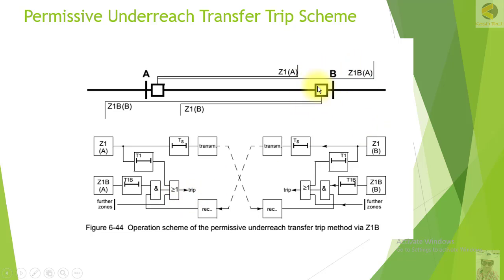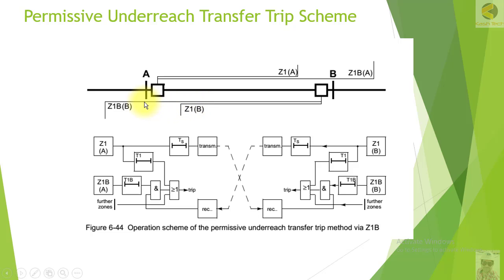Without this scheme, Station B trips instantaneously while Station A's relay would wait for Zone 2 time. This is the benefit of the permissive underreach transfer trip scheme. Now consider a fault in the reverse direction behind Station B: the relay at B will not pick up and will not send any permissive signal to Station A.